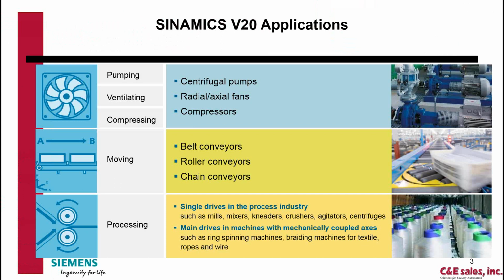V20 is a pretty basic drive for basic applications. Volts hertz type mode control, does not do any kind of vector control. So typically you'll see these in pumping, ventilation, and compressing, maybe some moving applications where speed isn't super critical, belt conveyors, roller conveyors, chain conveyors, and some processing, where you got a single drive, maybe with some mechanical interlocks or mechanical coupling between different motors. So everything has to mechanically follow the same speed. Again, it's not super tight speed regulation.